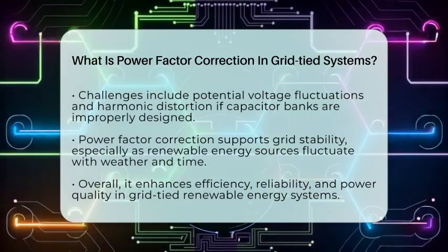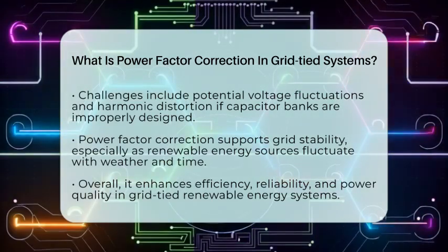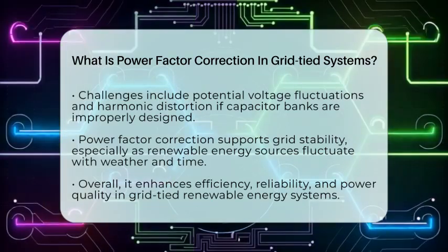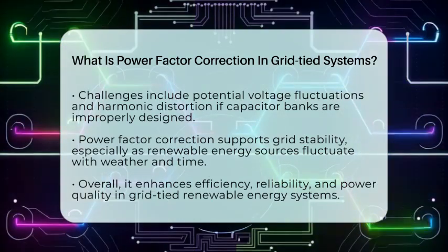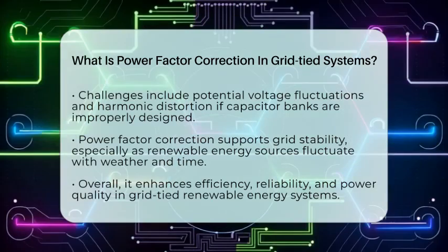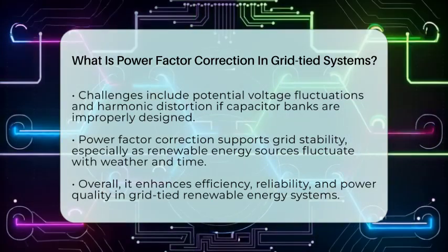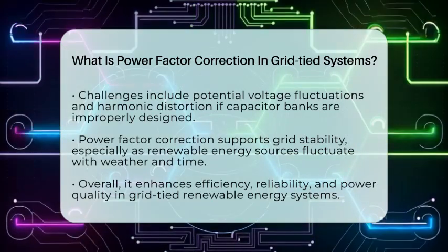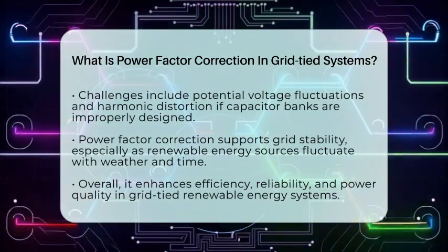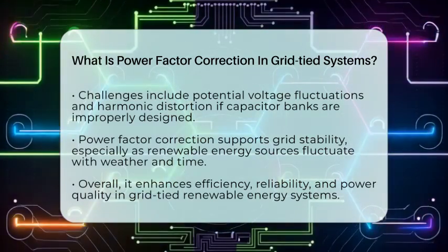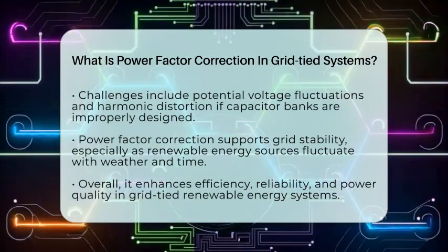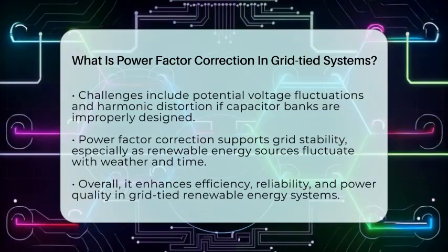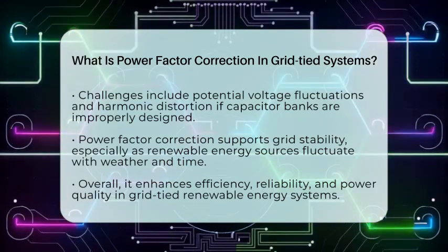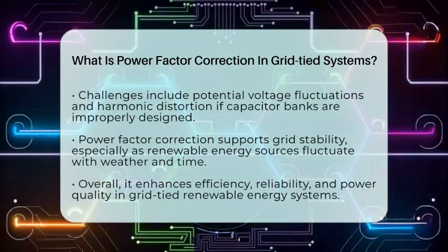stable and reliable. In summary, power factor correction in grid-tied systems is a key part of making renewable energy systems more efficient and reliable. It involves adding devices that supply or absorb reactive power to keep current and voltage in sync. This process helps reduce losses, improve power quality, and support the stability of the electrical grid as more renewable sources come online.